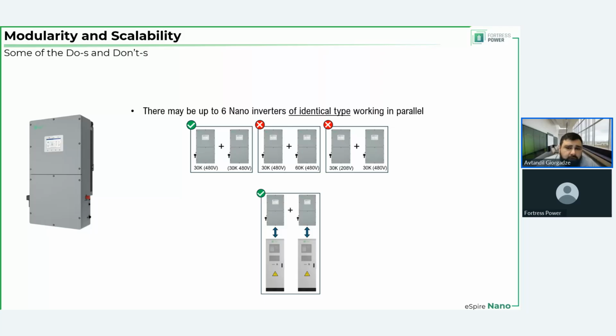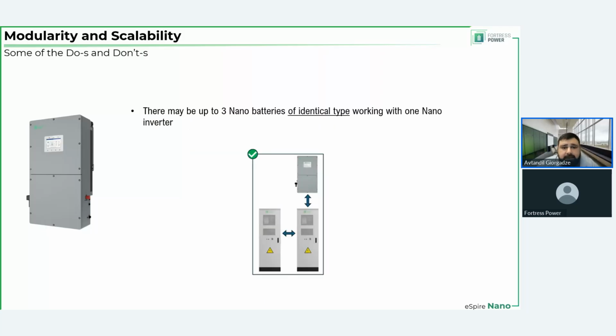Now, you can only have 6 Nano inverters working in parallel, and they must be of identical type. So you cannot mix different types of inverters. All of them must be of the same type, the same model. Each inverter can work with up to 3 batteries. By up to 3, we also count in 0, because you may have a situation when you have, let's say, 2 inverters working in parallel, and one of them does not have batteries at all, and the other one does. That is a possibility. You can do that.